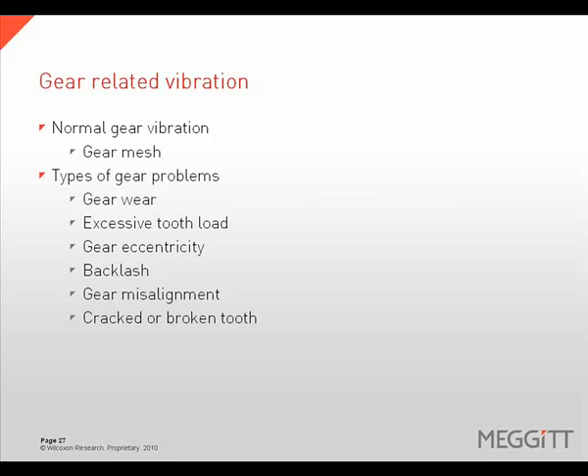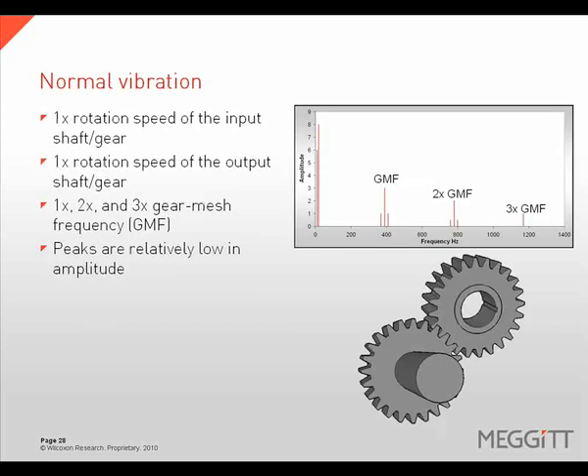Any gear set will generate a vibration response. Gear-related vibration can be normal, or it can be an indication of problems such as gear wear, gear misalignment, cracked or broken teeth, or other problems. It is normal for a gear set to generate vibration at its gear mesh frequency and harmonics — 1x, 2x, and 3x gear mesh frequency are all normal, but they should be at relatively low amplitudes.